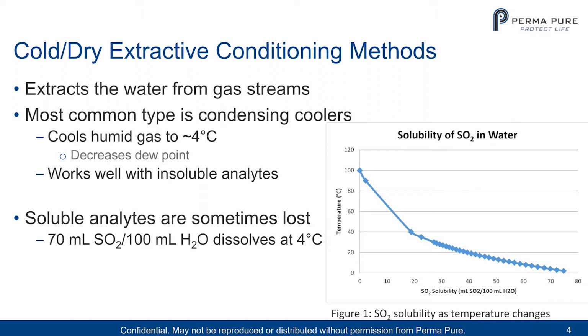One of the reasons SO2 is such a concentration point is because in many areas of the world where pollution is really an issue with horrible air quality, the requirements from the governments to eliminate SO2 are becoming stricter, and as a result, the levels of SO2 that need to be measured coming off the stack are actually much lower. So in the past, you might be able to live with 100 or 200 or 250 ppm SO2 in your exhaust gas. That's now no longer allowable.